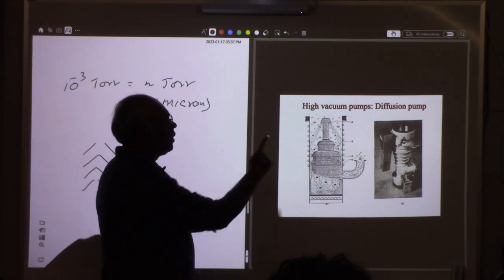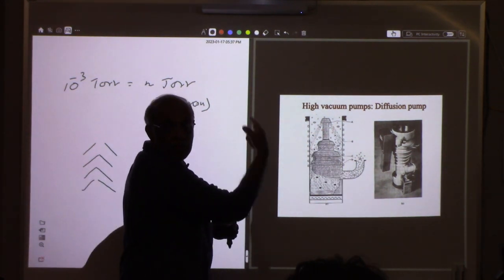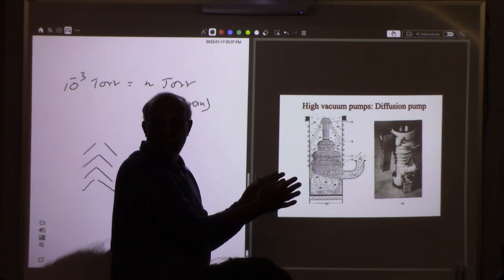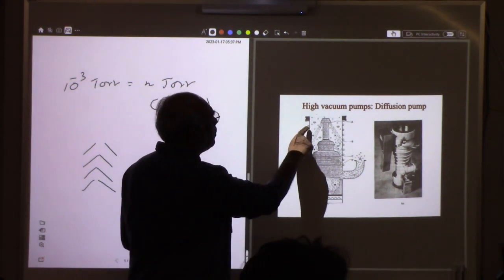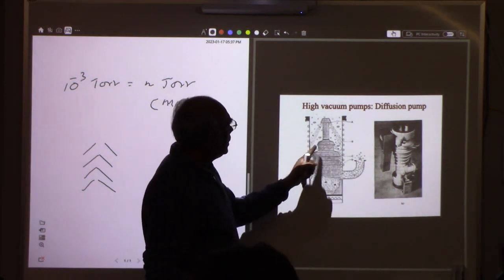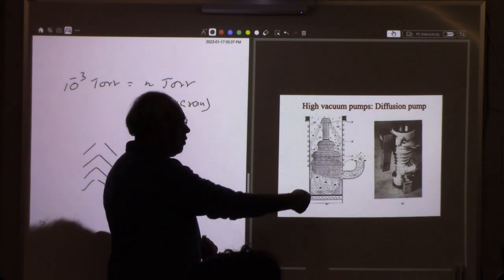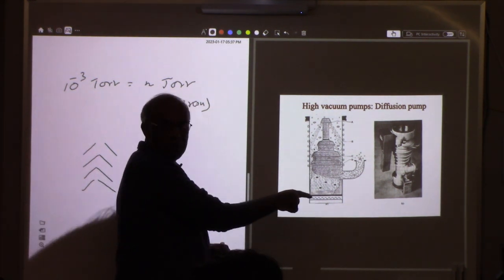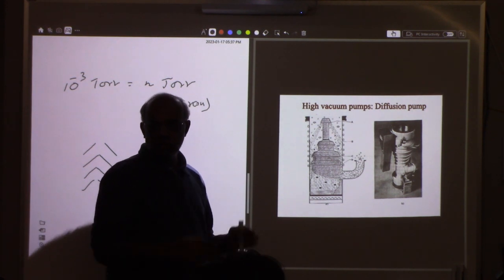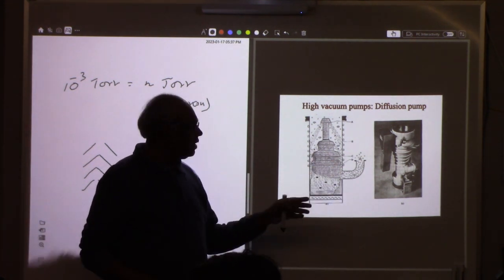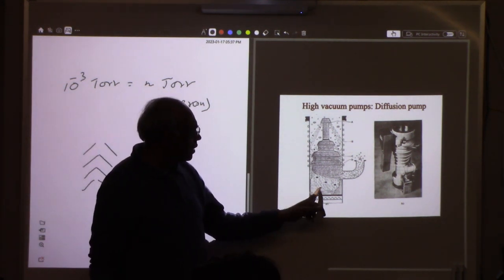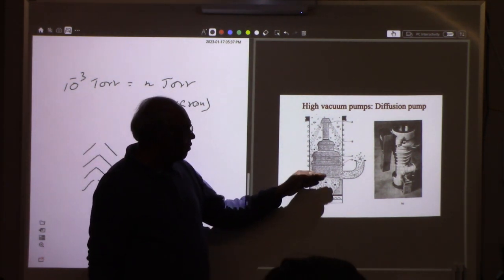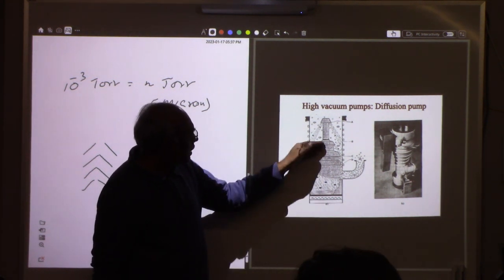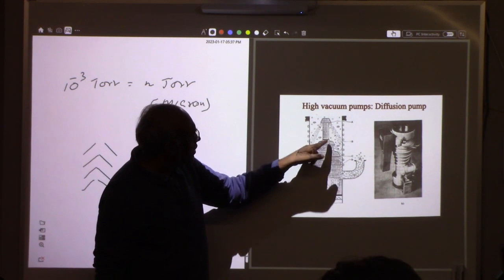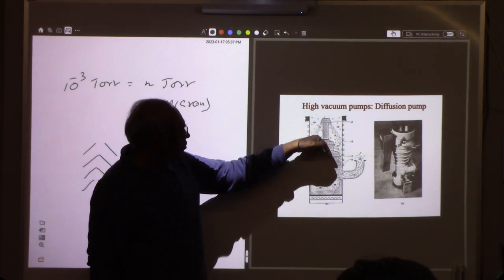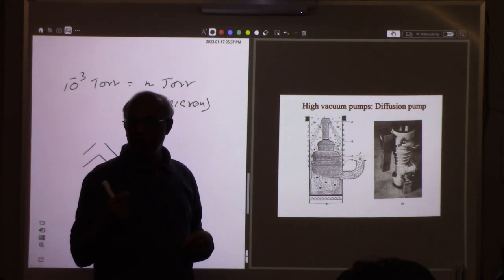So that's why sometimes you have to use some running water around this one to keep it cold. Otherwise, it becomes really too hot, right? These are for this running water. So whenever you have a diffusion pump, when you heat the filament, you have to start running the water. Otherwise, this becomes too hot. So then what happens is this oil vapor, right? It just moves here. So then it makes some jets through these tiny holes. So these jets are very high energetic jets of oil particles.